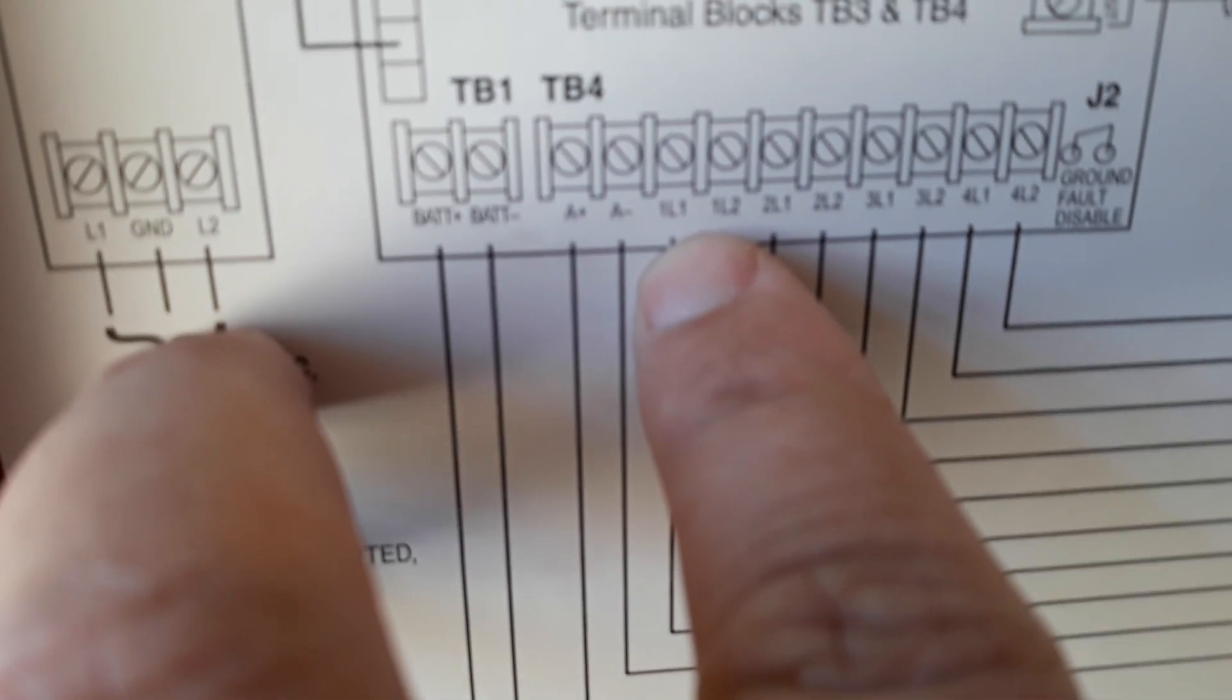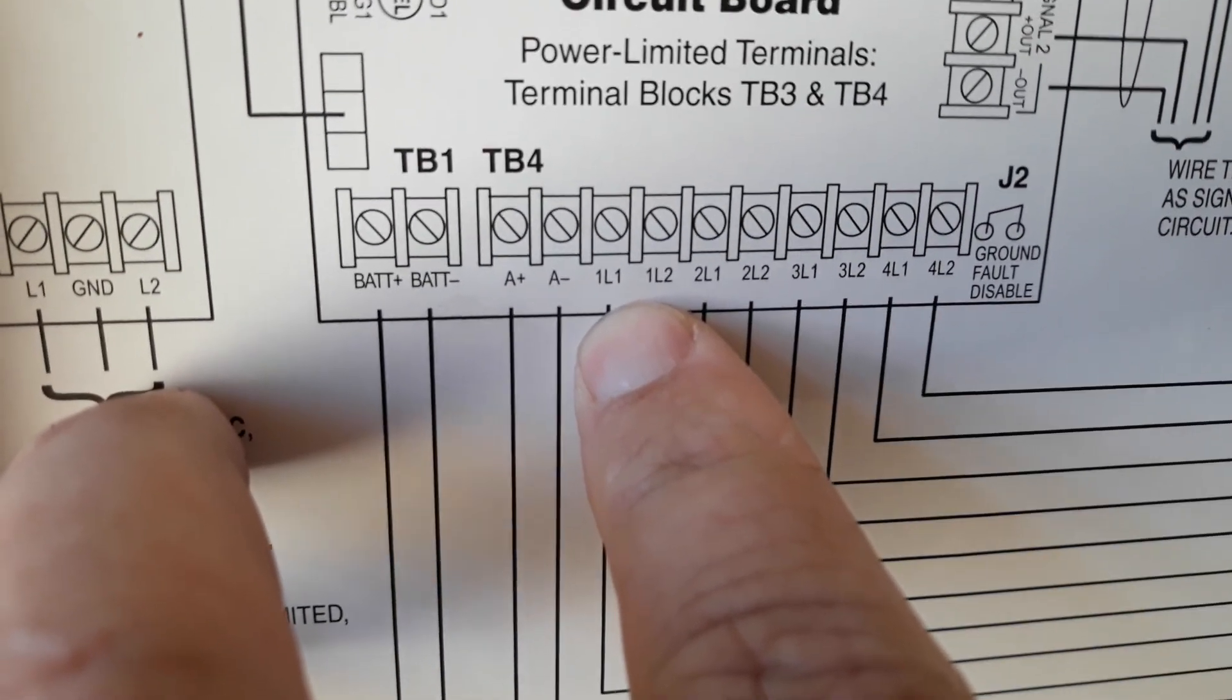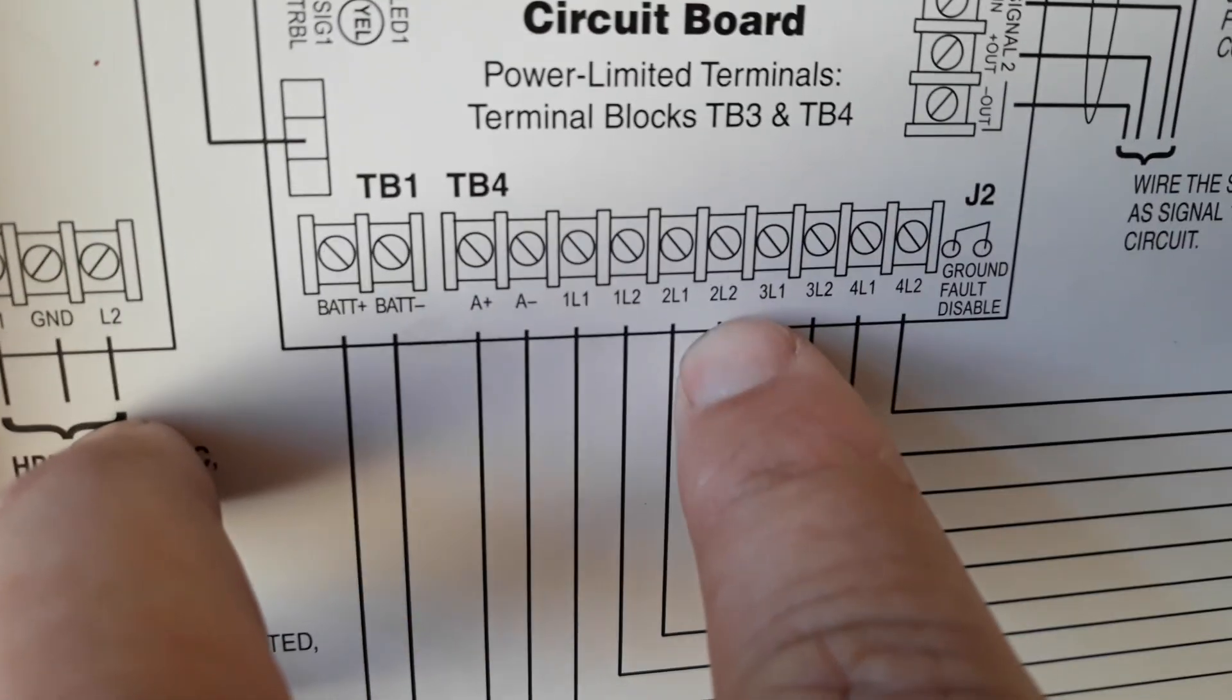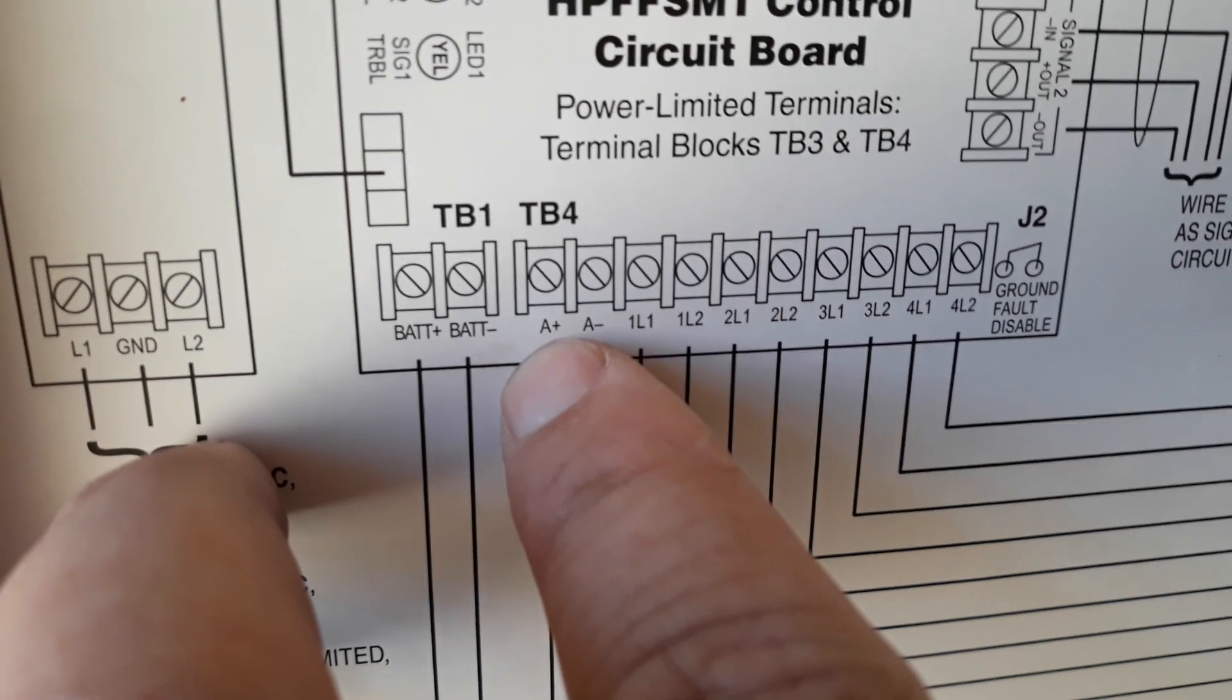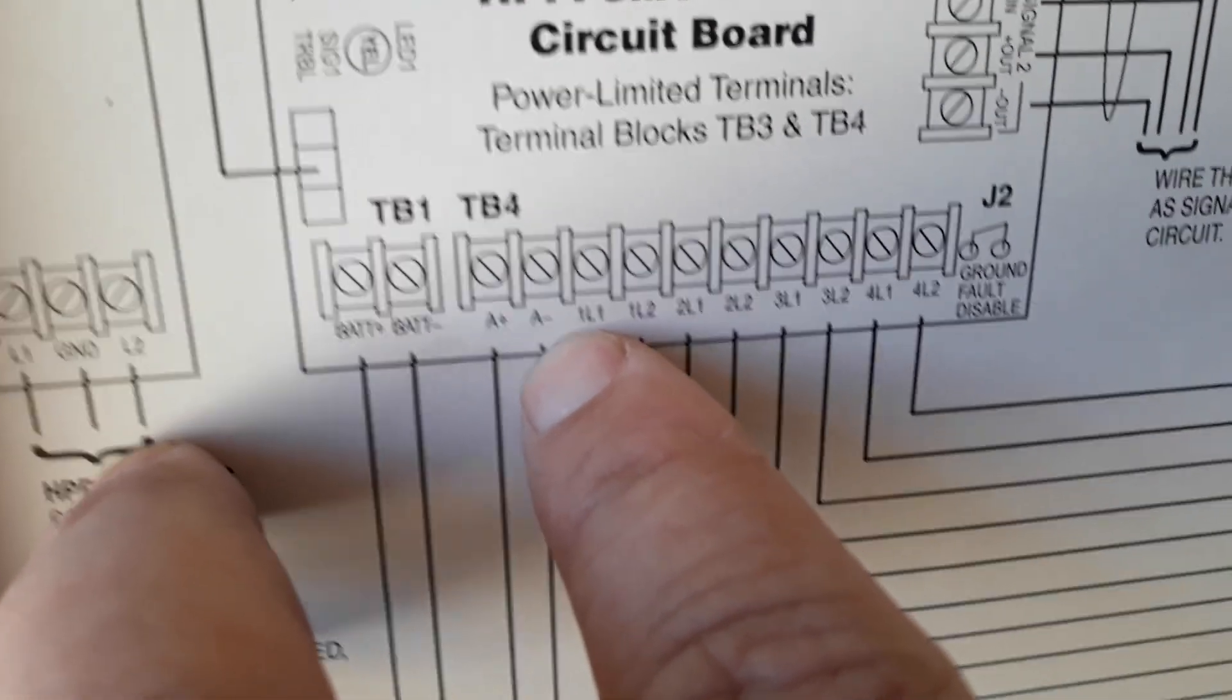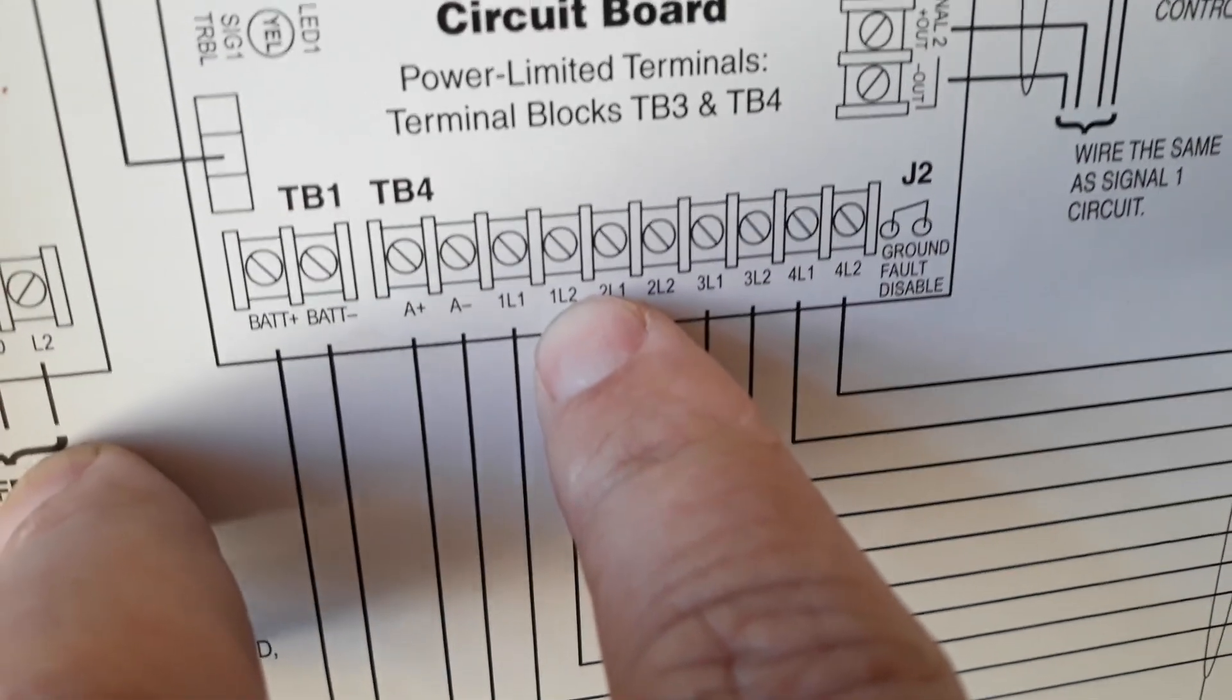But you've got to have the manual and a lot of people don't leave the manual anymore. So it says 1L1, 1L2. It wouldn't have been hard for them to put a minus and a plus, minus and a plus, minus and a plus. Because it doesn't stay the same pattern right here. See that's plus and then minus, plus and then minus. So you think, okay, well maybe they just did the same pattern. Plus and then minus. Now they flip-flopped it and went negative and plus.